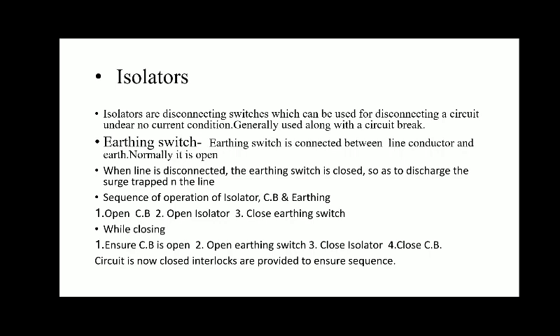Next, there is a sequence of isolators, circuit breakers, and earthing switches. When you want to disconnect the line, while opening, first open the circuit breaker, second open the isolator, and third close the earthing switch. While closing the line, when the fault is clear or everything is normal, the sequence is: first ensure the circuit breaker is open, second open the earthing switch, third close the isolator, and fourth close the circuit breaker. The circuit is now closed. Interlocks are provided to ensure such a sequence. So this is the sequence of closing and opening the line.